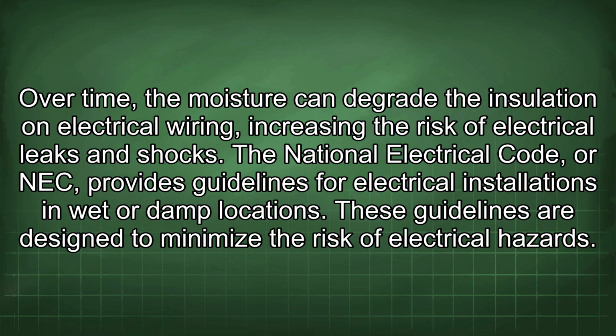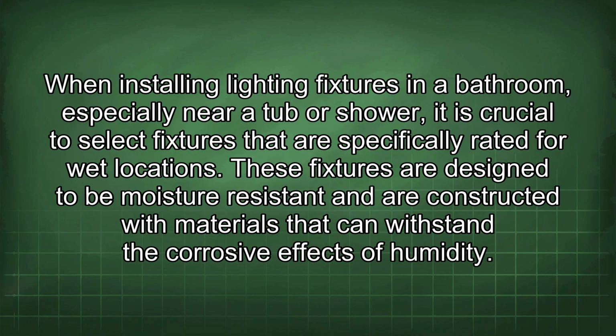The National Electrical Code, or NEC, provides guidelines for electrical installations in wet or damp locations. These guidelines are designed to minimize the risk of electrical hazards. When installing lighting fixtures in a bathroom, especially near a tub or shower, it is crucial to select fixtures that are specifically rated for wet locations.